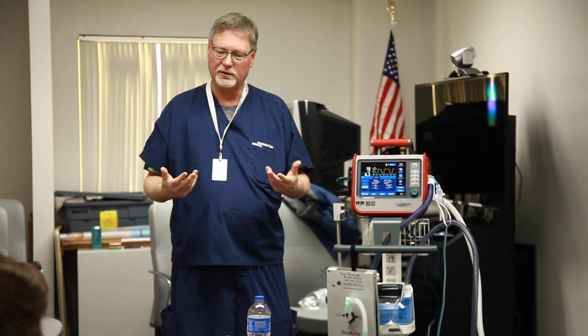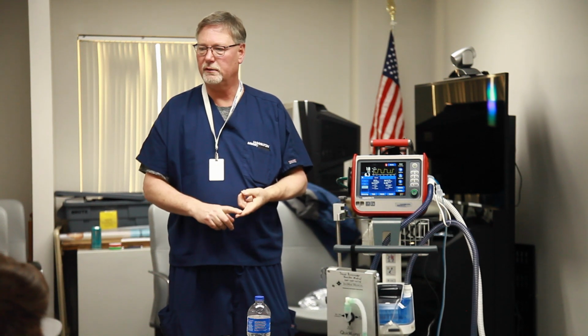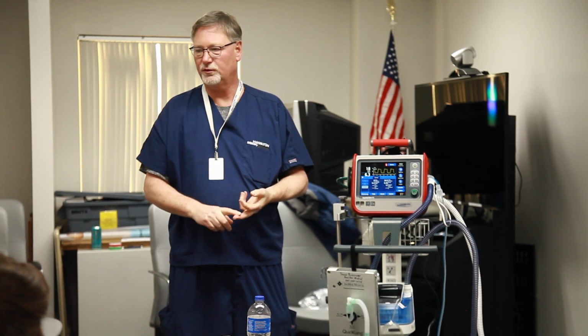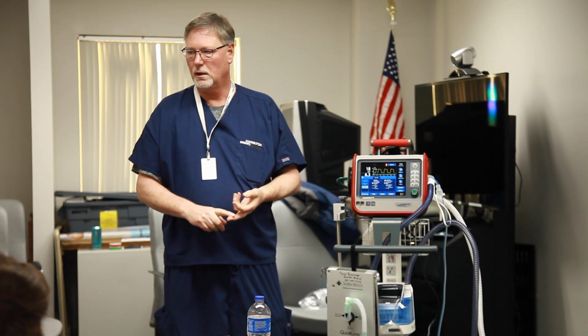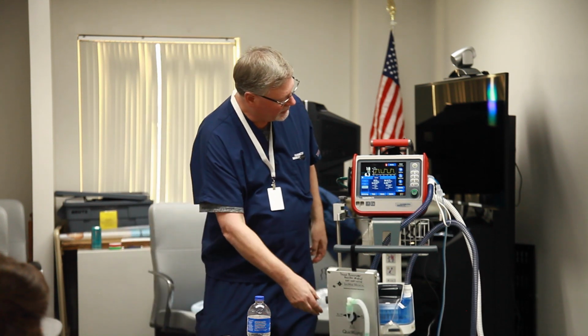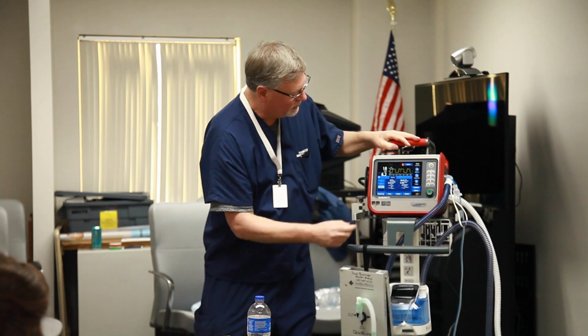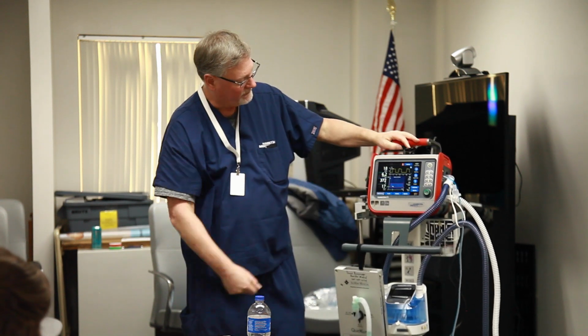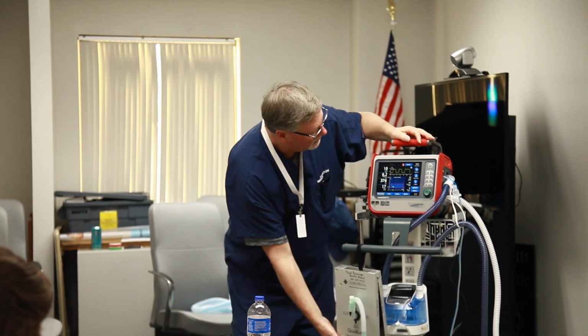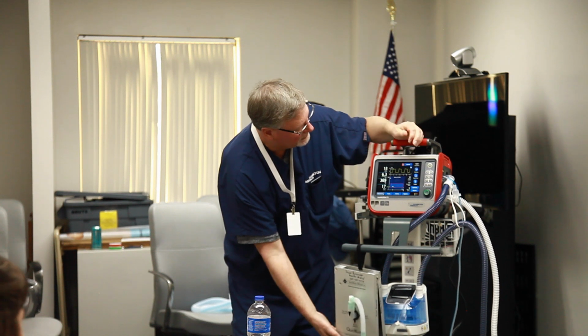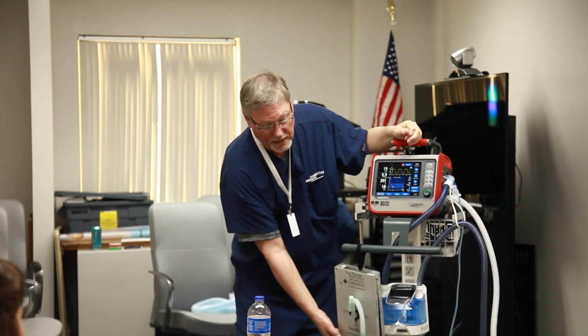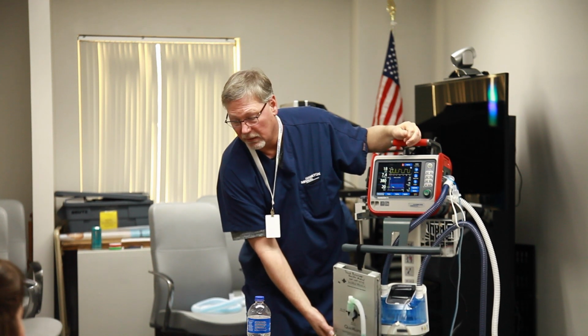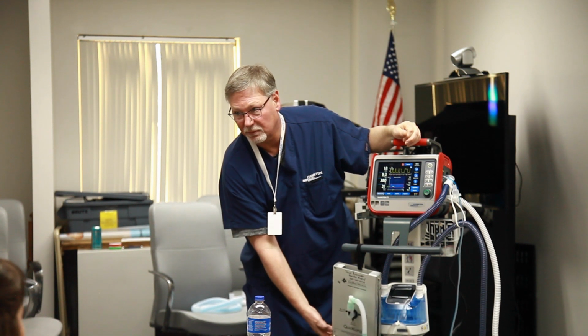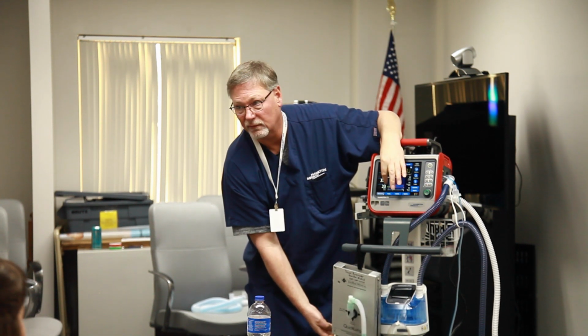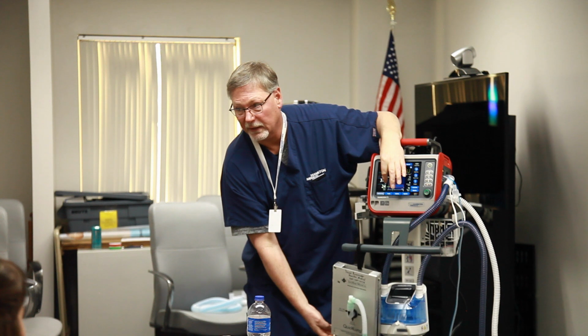What you're going to notice, it does two things. It decreases the work of breathing, and it decreases the force of breathing. By decreasing the work of breathing when I'm in ASV, you're going to notice what my pressure graphic looks like here. Now when you see a spontaneous effort, the little triangle underneath there, my I-time changes. Now it actually switches to a spontaneous mode that's targeting that tidal volume.